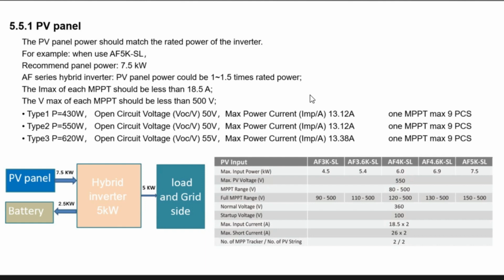Okay, we're back to the system design manually. So the first thing you will check is the panels' VOC and the panels' IMP data, and normally for the hybrid inverter, all these panels should be connected in series. So the current is the same, and the voltage should be multiplied by the panel quantity.